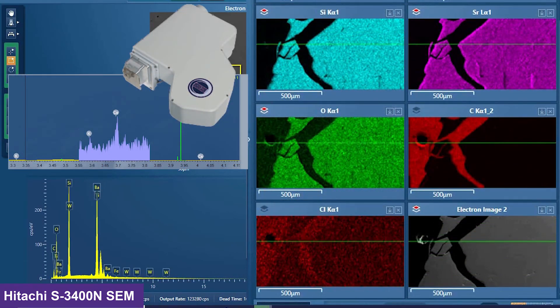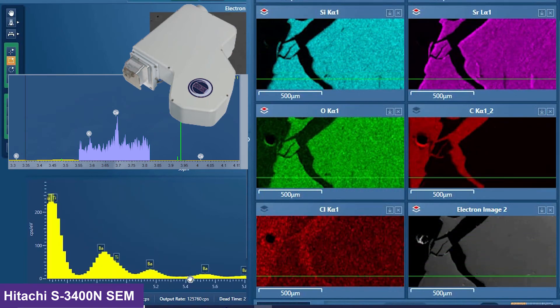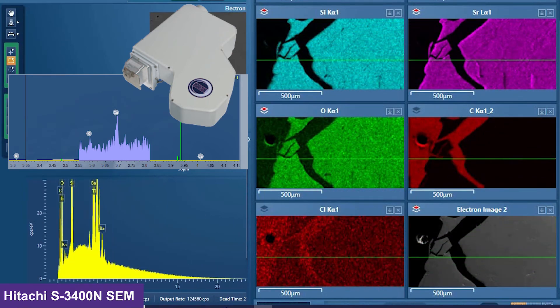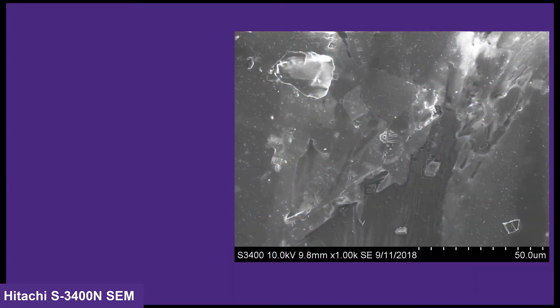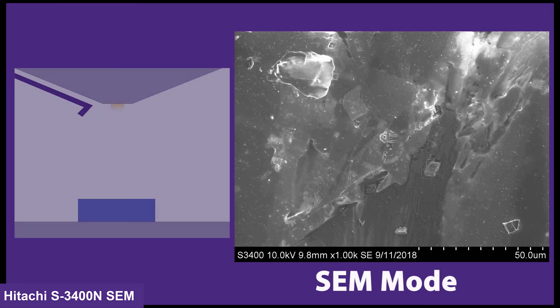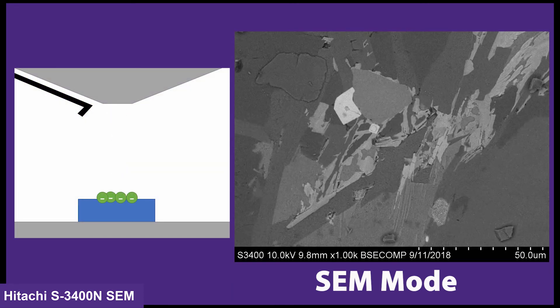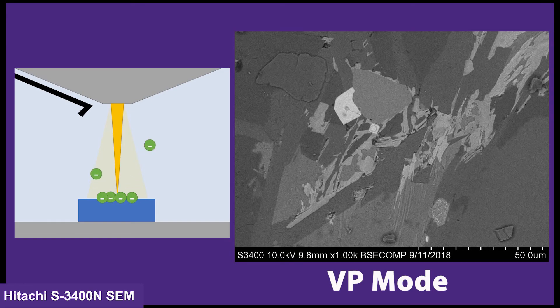This microscope also has a WDS system, or Wavelength Dispersive X-ray Spectroscopy System. With this system, you can do compositional analysis down to 0.01 weight percent. It is also equipped with a variable pressure mode, a technique that allows you to image uncoated, non-conductive samples without charging artifacts. This introduces air or gas into the chamber to create positively charged gas ions to neutralize negative charge buildup on the surface of the sample.